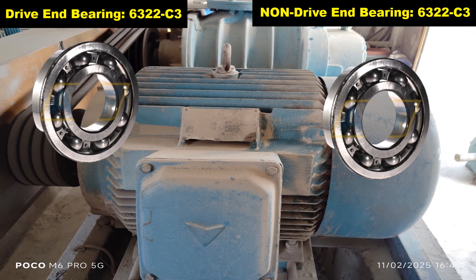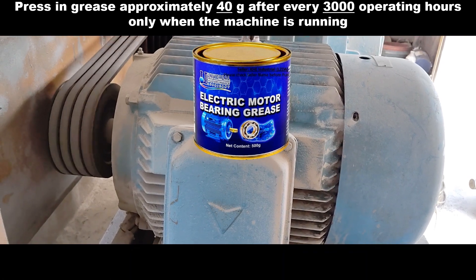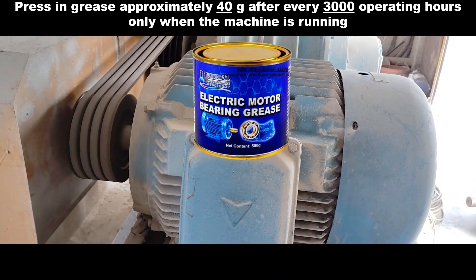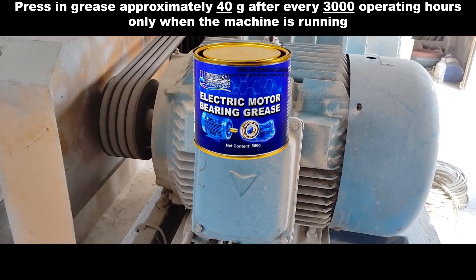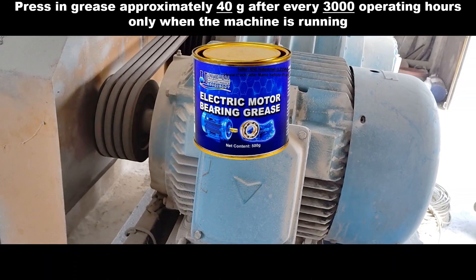In this motor, the bearings used in the drive-end and non-drive-end are 6322-C3. This means that every 3000 hours of operation you need to add approximately 40 grams of grease to the bearings of the motor, and the motor must be in running condition when you apply the grease.